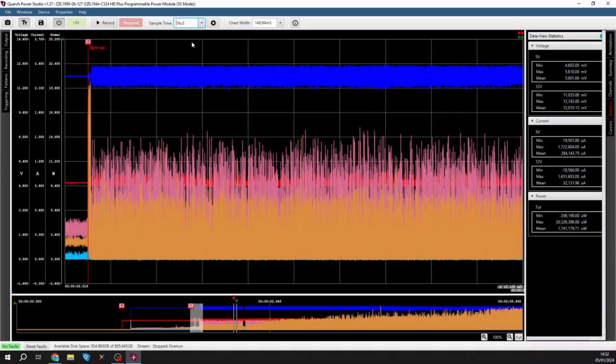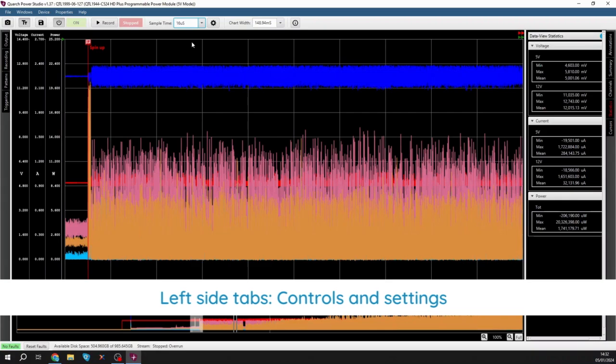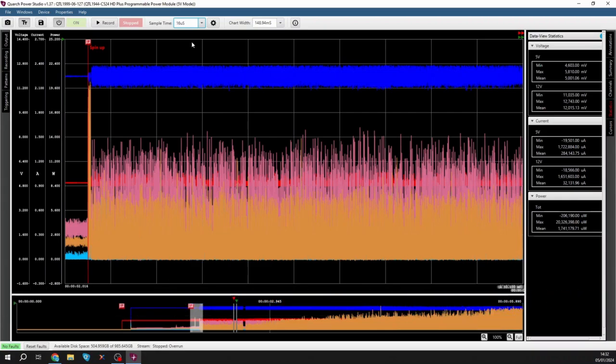What that means is, if you ask for a slower sample rate, we're never throwing away data. We're always averaging together, so we get very accurate power readings. Now, this particular device is multi-rate, or at least it can be multi-rate. Sorry, this one is not. This is a single-rate device. As we can see here, there's only one group. It is the analogs, and it's currently set to 16.